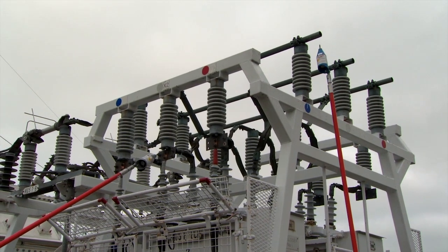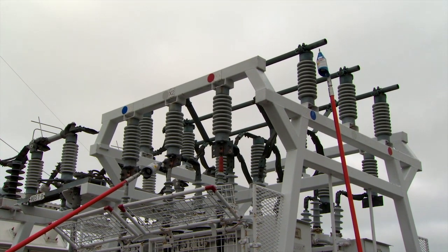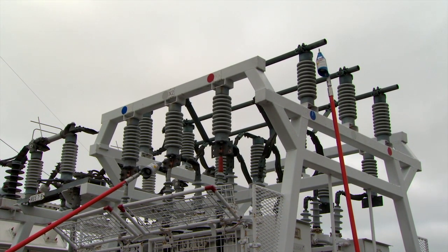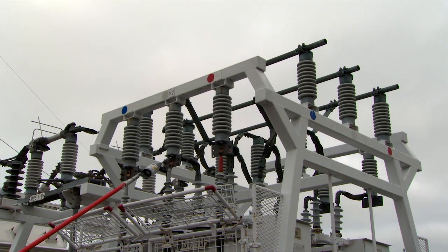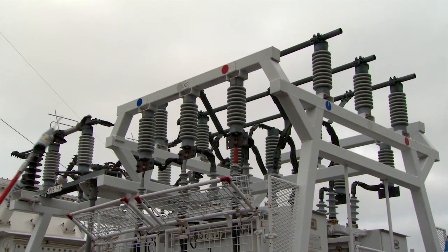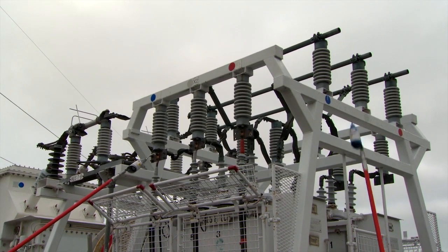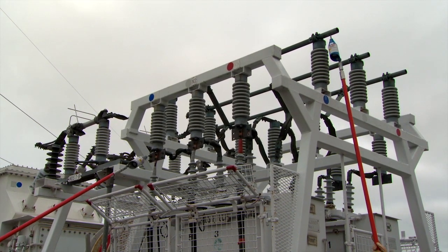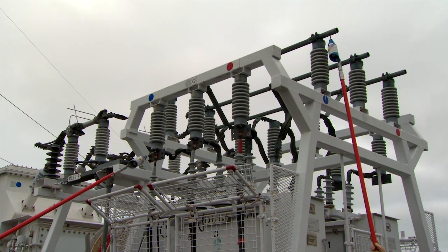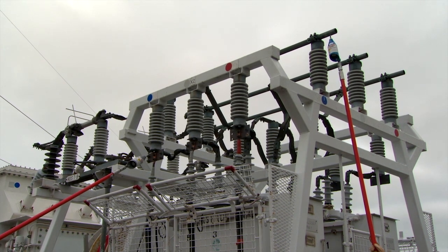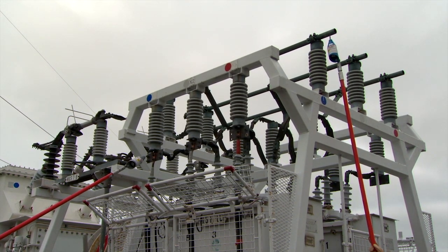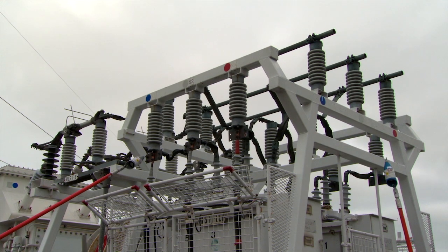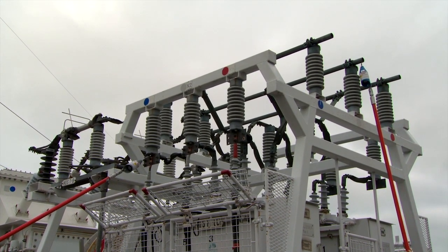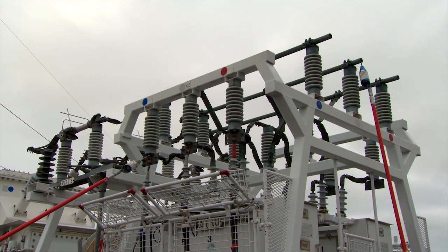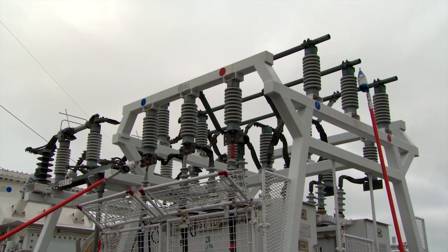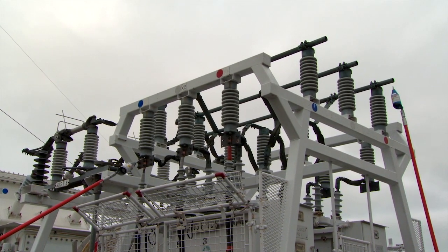After all lines are confirmed as being energized, place the transmitter on the first conductor to be phase checked and wait for the beeping tone and flashing lights to stop. One light will remain on, indicating the unit is transmitting. Then place the receiver on the opposite side of the open point. When placed on an energized conductor, the unit will beep once when voltage is detected, and one LED light of the receiver will turn on to signal the unit is operating in the receive mode.